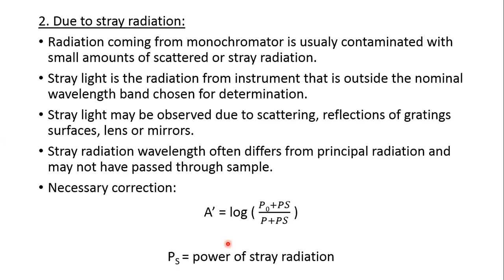When stray radiation is present, a correction can be made to rectify the result and modify the calculation by including the absorbance expression A equals log of P naught plus PS over P plus PS, where PS is the power of the stray radiation. So we add the power of the stray radiation to both the incident light and the transmitted light, so that the correction factor is included in the calculations. We can also see the correlation of absorbance and concentration and the effect of stray light. When there is 0% stray light, linearity is observed. But as the percentage of stray radiation increases, the deviation from linearity also increases. At 0.2%, it is a little higher. At 1%, the deviation increases a little more. And at 5%, even more deviation is observed.